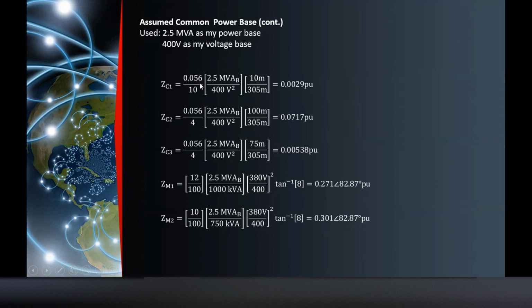But since you only used 10 meters from the terminal of the transformer to the bus bar, the impedance is definitely different. So you will get 0.0029 per unit. And for cable 2, 0.056, same 250 mm, 4 sets. It's just that it is 100 meters, so you will get 0.0717 per unit. And for cable 3, same size, divide by 4 sets. Only the length differs, 75 divided by 305, you will get 0.00538 per unit.